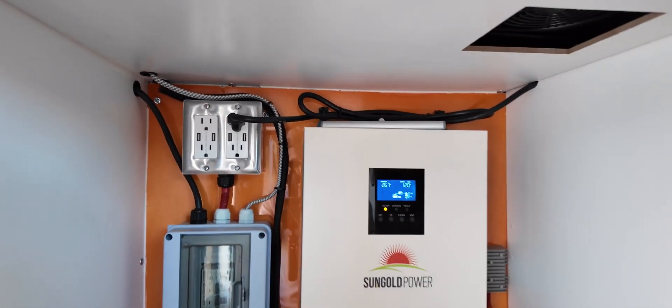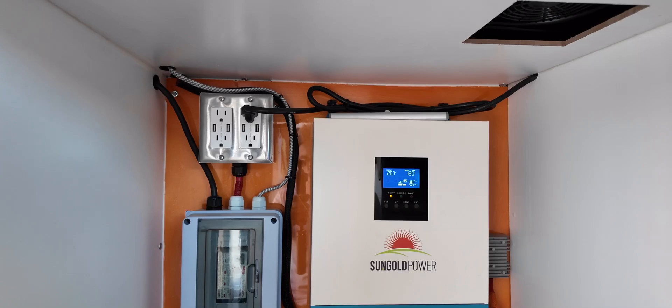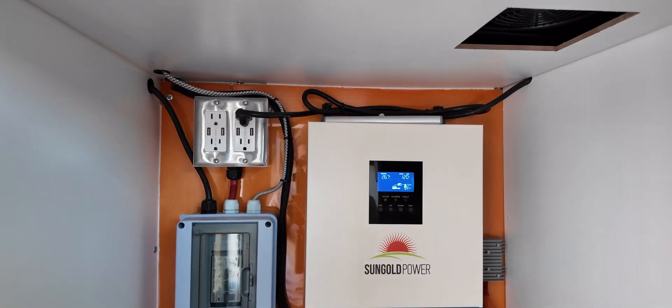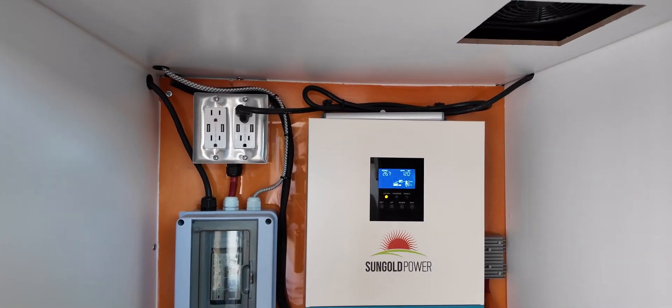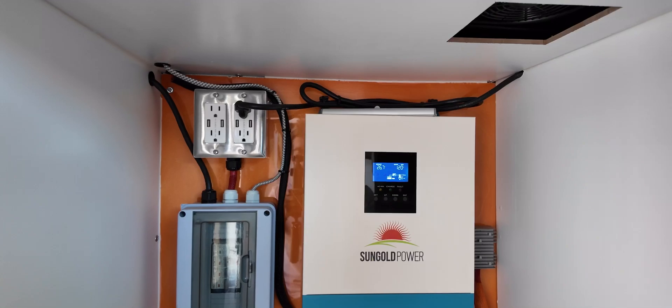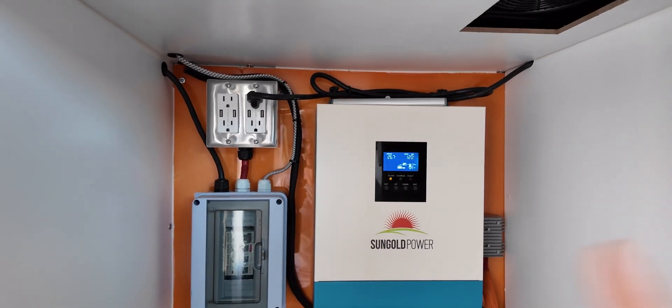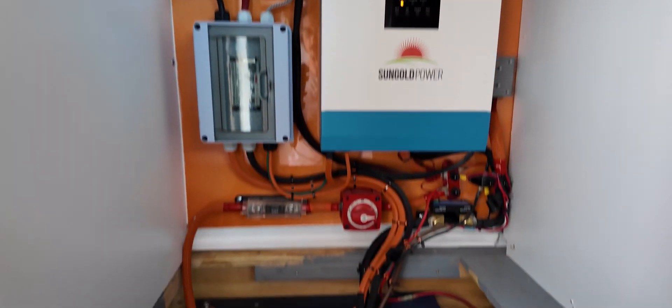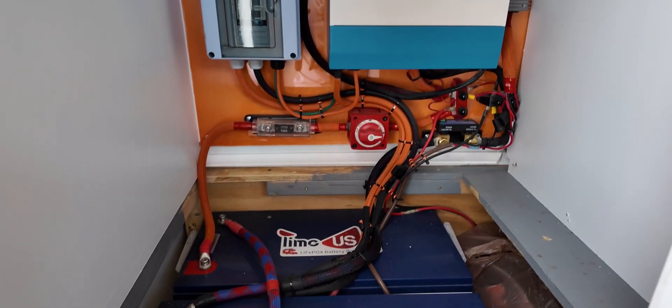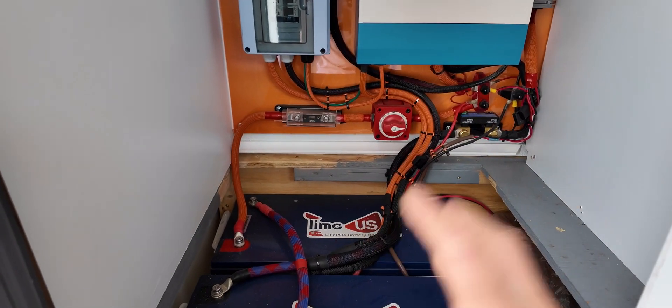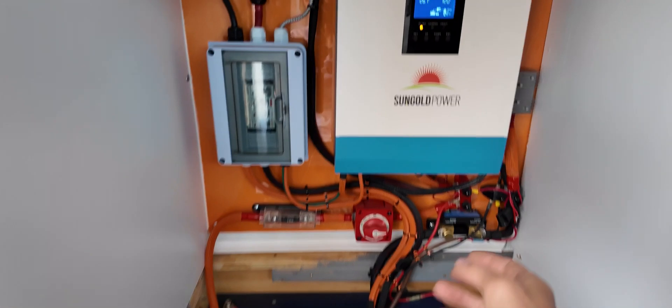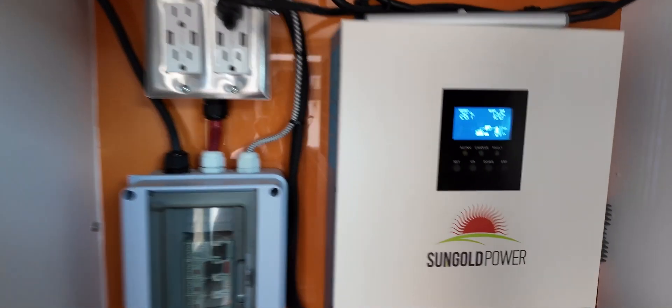Just to make a note, you always want to shut off your solar panels when you're switching your battery bank. You want to make sure that the solar panels are not outputting energy without batteries connected. When you're installing batteries, you always want to have the batteries connected first before you go ahead and connect solar energy.